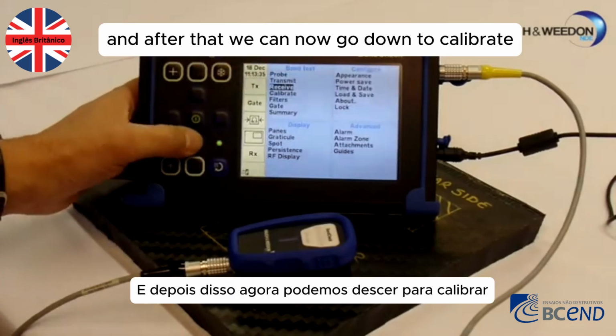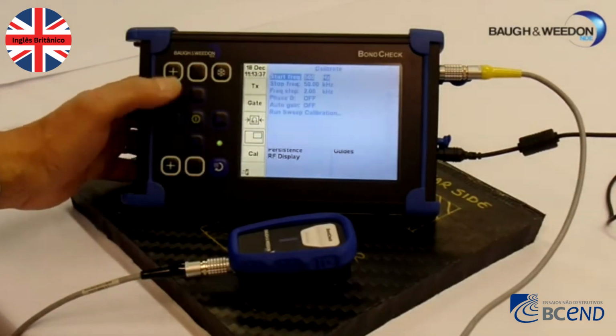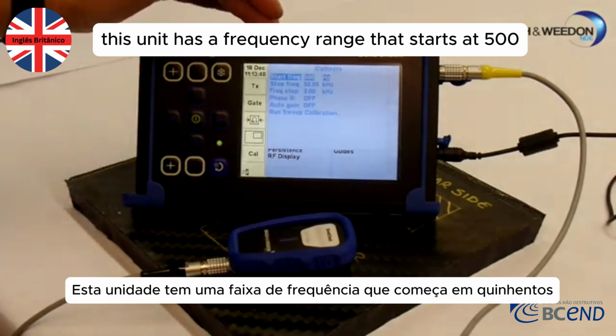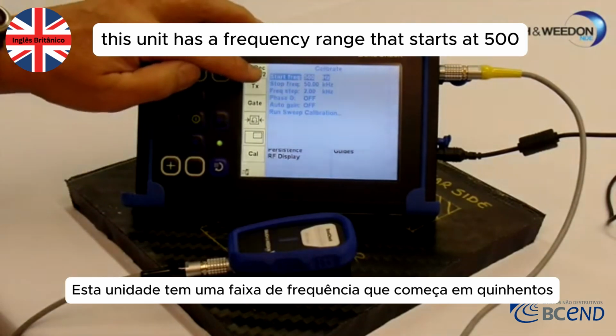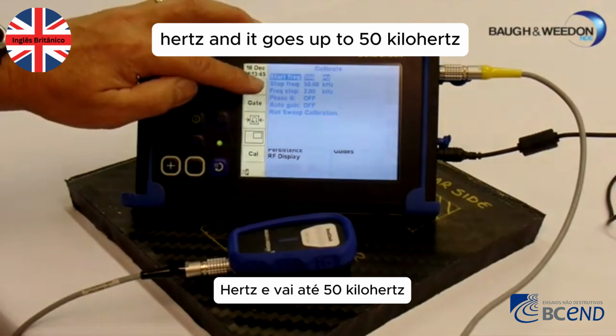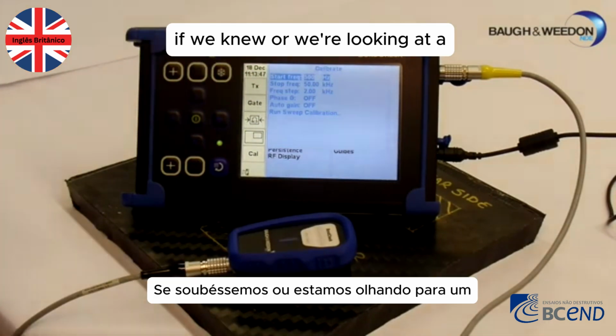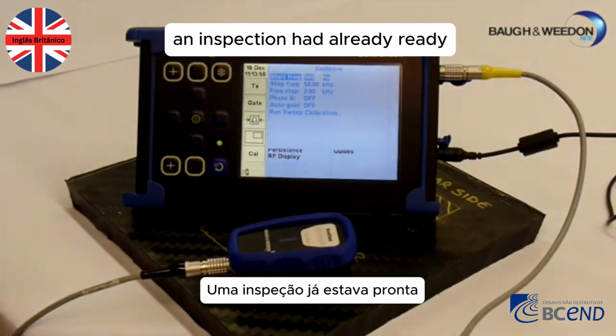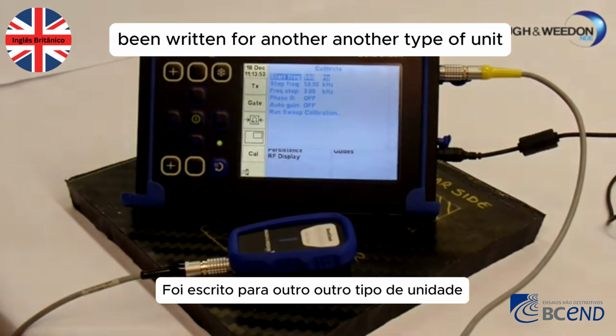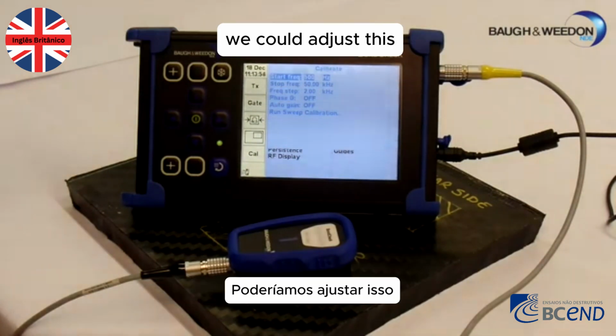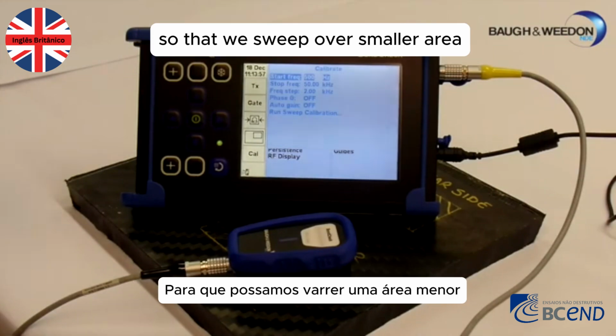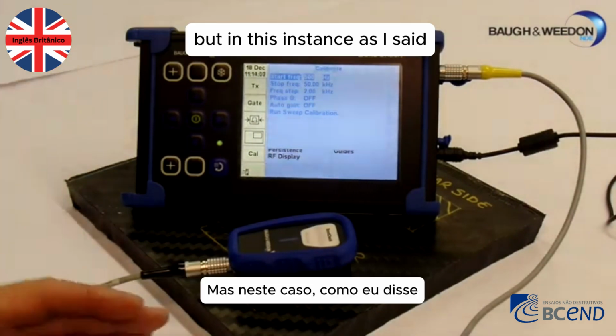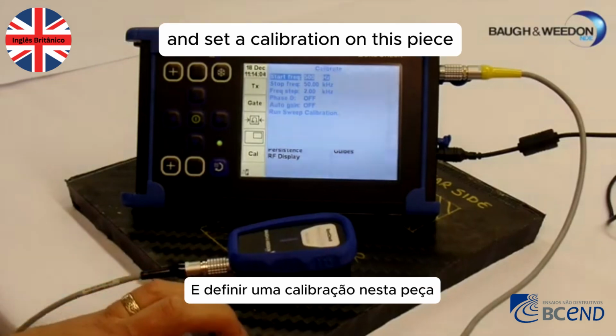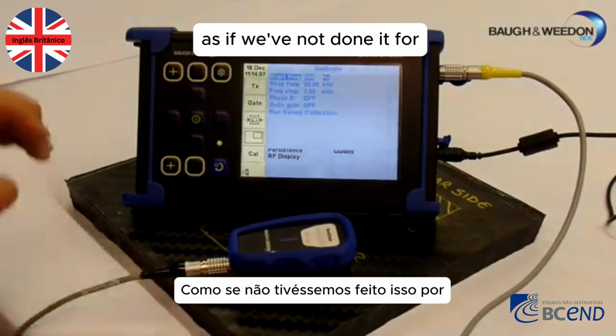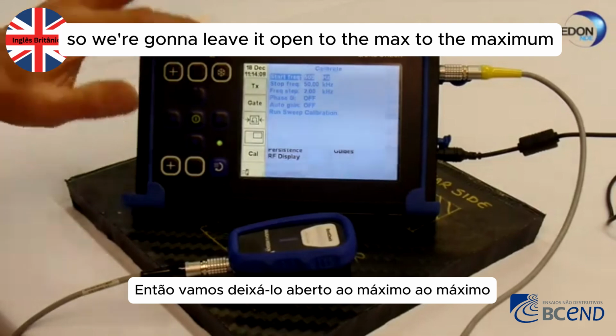Come out of there, we can now go down to calibrate, select calibrate. This unit has a frequency range that starts at 500 Hertz and it goes up to 50 kilohertz. If we knew, or we're looking at an inspection that had already been written for another type of unit, we could adjust this so that we sweep over a smaller area. But in this instance, as I said, we're going to carry out a calibration on this piece as if we'd not done it before. So we're going to leave it open to the maximum.